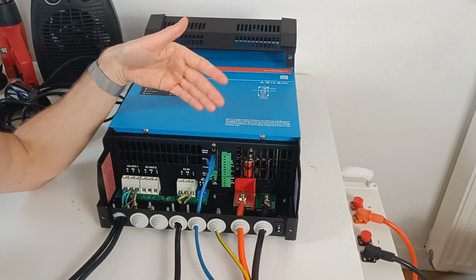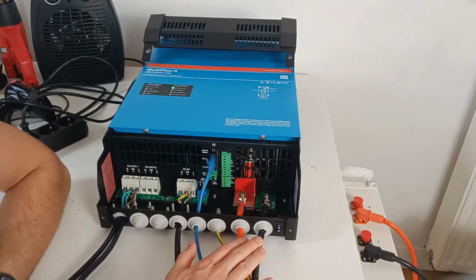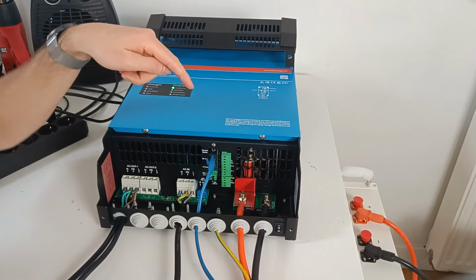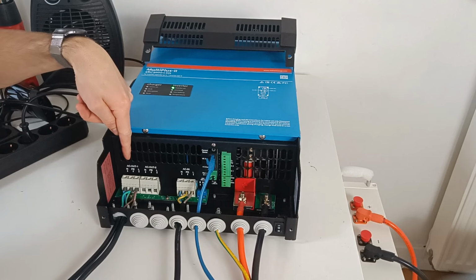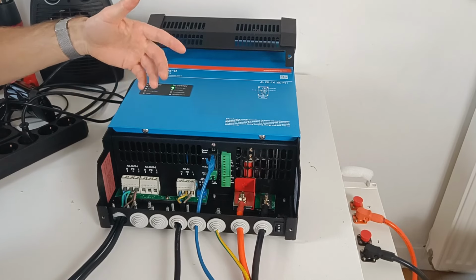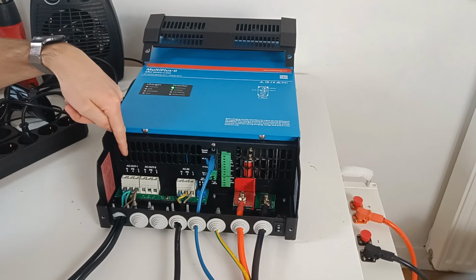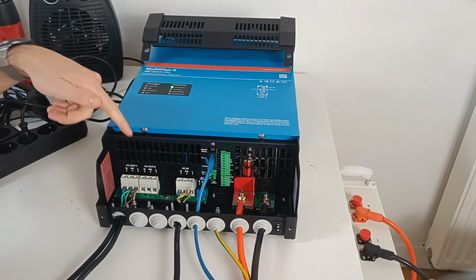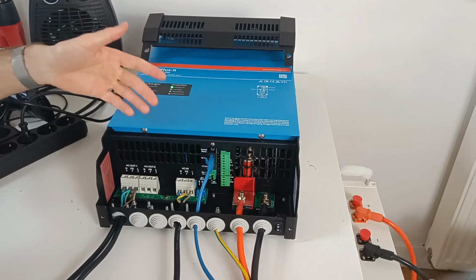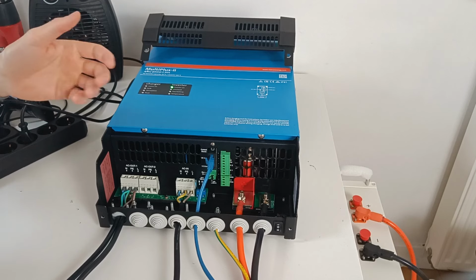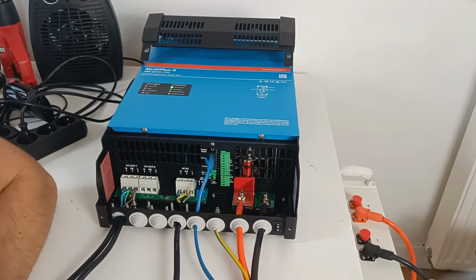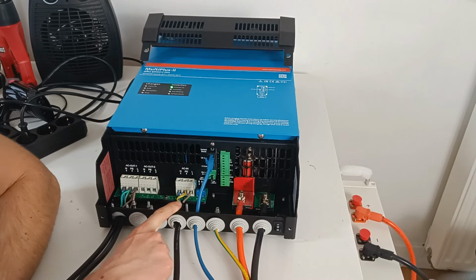Let's take a look at the connections. This is the main battery input. AC out 1. This output powers your essential appliances, whether the grid is up or down. This output stays on. AC out 2 is for non-critical loads. It only works when you have AC power coming in from the grid or a generator on AC in.